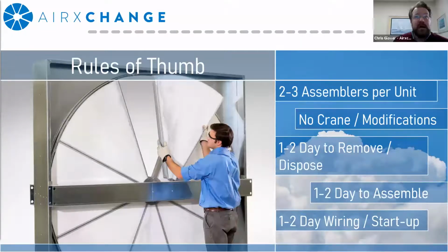So just quick rules of thumb when you're looking at a replacement project. For the majority of projects that I've been involved with, we typically recommend having 2 to 3 people available for removal and assembly, and maybe 1 to 2 people for repair. In most cases, we find that adding more people usually doesn't cut down on the labor, because you're typically working within the tight space constraints of the existing HVAC cabinet, and the tight constraints of a penthouse or a mechanical room. So there's only really so many people that you can throw into those spaces.